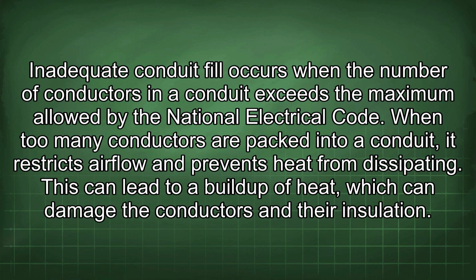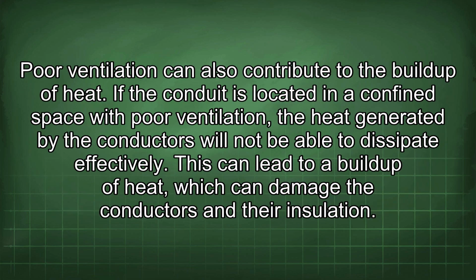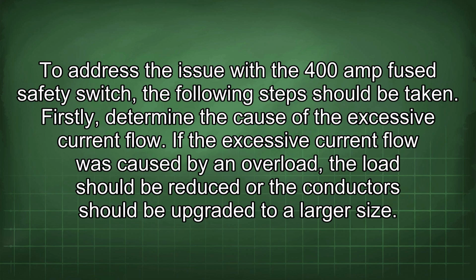Inadequate conduit fill occurs when the number of conductors in a conduit exceeds the maximum allowed by the National Electrical Code. When too many conductors are packed into a conduit, it restricts airflow and prevents heat from dissipating. This can lead to a buildup of heat, which can damage the conductors and their insulation. Poor ventilation can also contribute to the buildup of heat. If the conduit is located in a confined space with poor ventilation, the heat generated by the conductors will not be able to dissipate effectively. This can lead to a buildup of heat, which can damage the conductors and their insulation. To address the issue with the 400 amp fused safety switch, the following steps should be taken. Firstly, determine the cause of the excessive current flow.